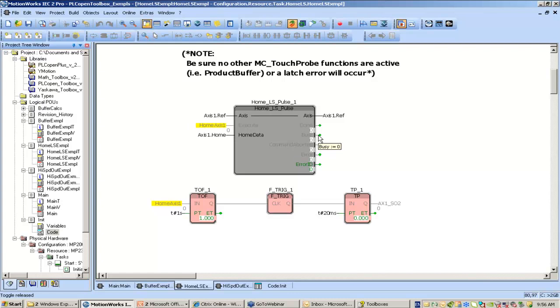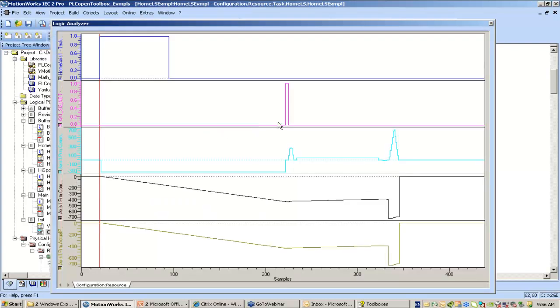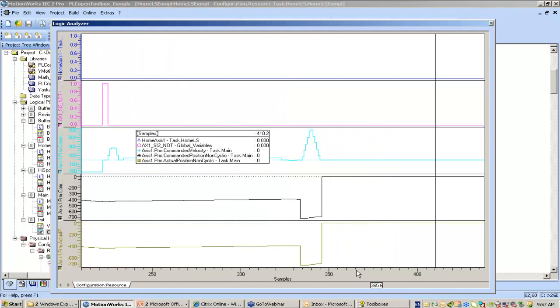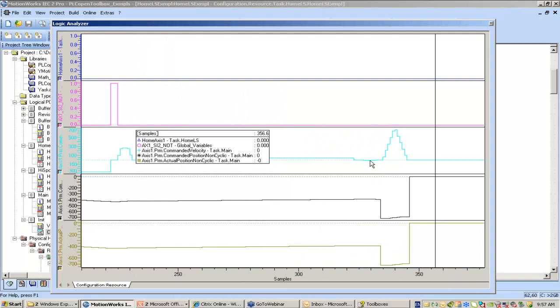Let's simply trigger this. While it's searching, you'll see that it is busy, and then done came on for one scan. Looking at the logic analyzer: here's where it started searching — the cyan value is our command velocity, searching in the negative direction. It found our end-of-travel limit, did a little backup move to get off that limit, then reversed direction. It started creeping in the positive direction until it found the C channel, at which point it went back to the C channel — you can see just a little bit of negative velocity as it stops, backs up, and returns to the position of the C channel. Then it makes its final offset move forward and sets position to zero.